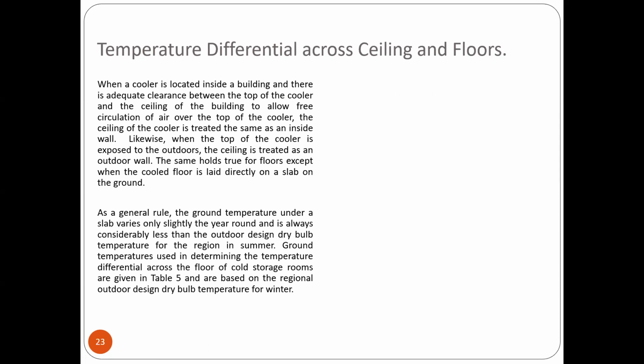Okay, inside temperature. Likewise, when the top of the cooler is exposed to outdoor, the ceiling is treated as outdoor wall. The same holds true for floors except when the cold floor is laid directly on a slab on the ground. So meron tayong ground temperature, di ba? As a general rule, the ground temperature under a slab varies only slightly the year round. It is always considerably less than the outdoor dry bulb temperature for the region in summer. Ground temperatures used in determining the temperature differential across the floor of the cold storage are given in table 5 and are based on regional outdoor design dry bulb temperature.